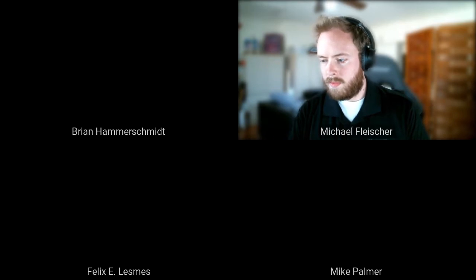Okay, yes. I am assuming this is about an insulation resistance test. If it's not related, please clarify in the chat. So I'm going to answer based on an insulation resistance test, following IEC recommendations. In a healthy system, insulation resistance should be over 1 megaohm. That is what we should expect and we should be measuring, as Brian shared in the presentation. So even if it's positive or negative, it should be over 1 megaohm if we expect to qualify a system as healthy.